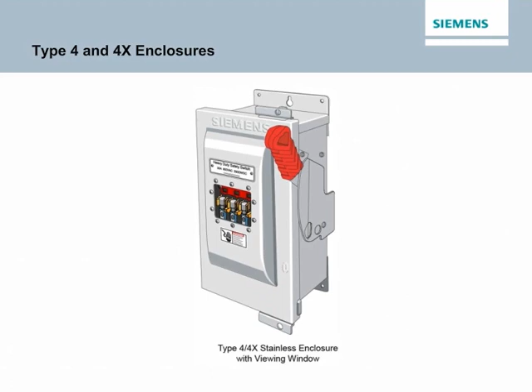Type 4 enclosures are intended for indoor or outdoor use, primarily to provide a degree of protection against windblown dust, rain, splashing water, hose-directed water, and damage from external ice formations. They are not intended to provide protection against conditions such as internal condensation or internal icing. Type 4X enclosures are made of a material such as stainless steel and are intended primarily to provide a high degree of protection against corrosion, windblown dust and rain, splashing water, and hose-directed water.